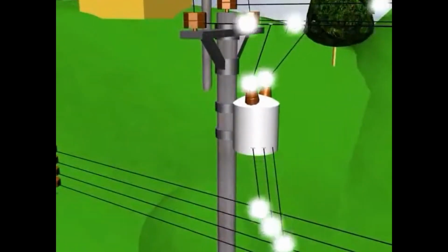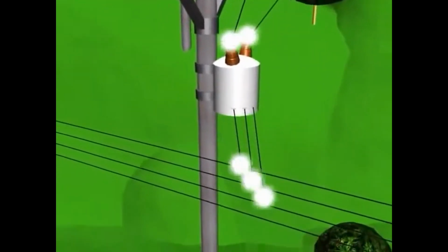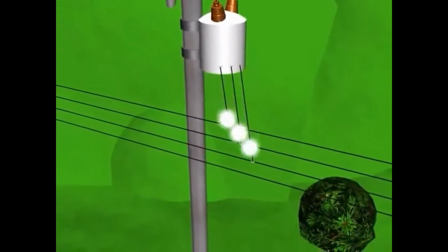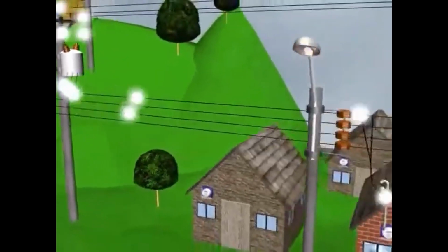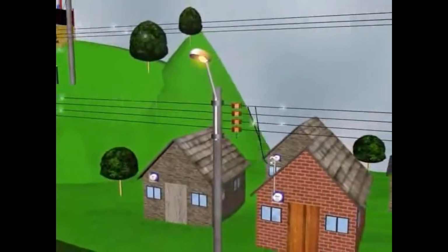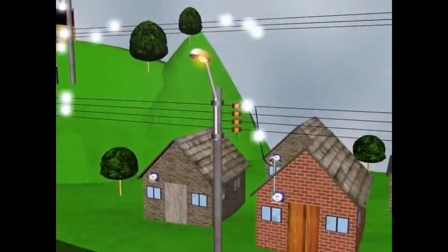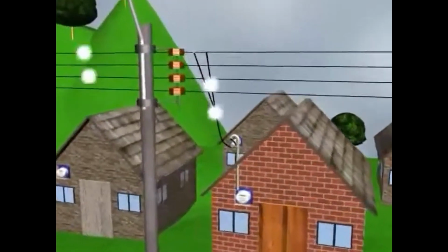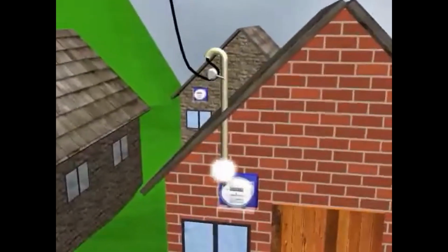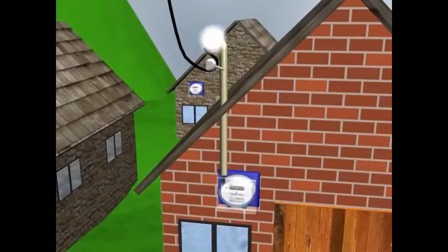127 volts with a range of plus or minus 10%, which ends up being a range of 114 to 139 volts in secondary lines, and this is the voltage, ladies and gentlemen, that reaches our homes, and it's what we consume daily.